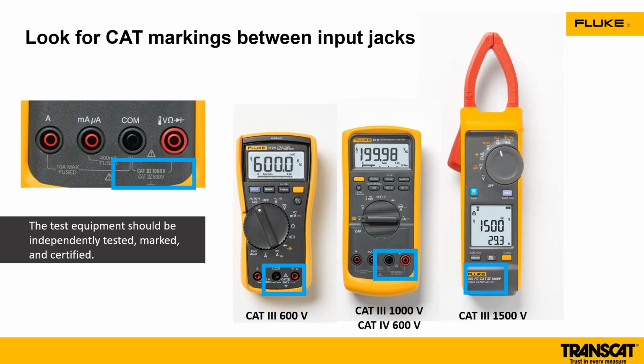Now, where can you find this? This is typically near the input jacks of your meter. As you can see on this slide on the left, you can see the category 3 1000 volt, category 4 600. On the other 2 meters and in our clamp meter, you can see it also at the input jacks. Now our clamp meter, this one here, is designed for category 3 1500 volt. So just know those markings, know where they're at, because that's really the key win with that IEC 61010 standard.